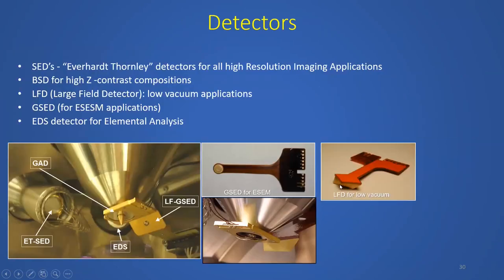Okay, so now coming to detectors. These are the detectors which are responsible for collecting the signals that are generated as a result of the interaction with the specimen. So you can have a secondary electron detector, you have a backscattered electron detector. Different manufacturers have different names for these detectors. The most commonly used detector is the Everhart Thornley detector, or the secondary electron detector. This detector is used for collecting the secondary electrons generated as a result of the interaction.